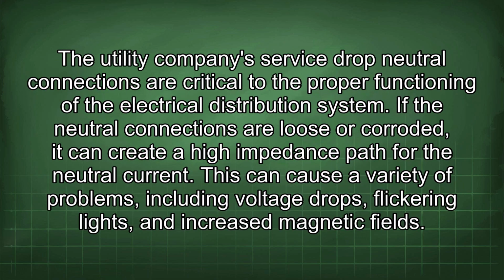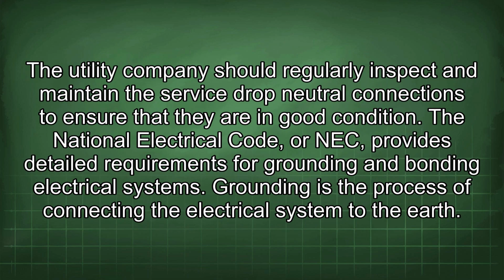The utility company's service drop neutral connections are critical to the proper functioning of the electrical distribution system. If the neutral connections are loose or corroded, it can create a high impedance path for the neutral current. This can cause a variety of problems, including voltage drops, flickering lights, and increased magnetic fields. The utility company should regularly inspect and maintain the service drop neutral connections to ensure that they are in good condition. The National Electrical Code, or NEC, provides detailed requirements for grounding and bonding electrical systems.